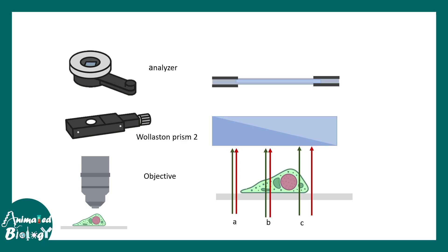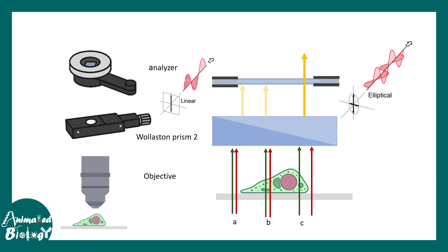Let us consider three scenarios A, B, and C. In scenario A, both ordinary and extraordinary light pass through the slide and reach the second Wollaston prism after the objective. In scenario B, both beams pass through regions of the same refractive index, so there is no optical path difference. In scenario C, there is an optical path difference because the ordinary and extraordinary light pass through regions where refractive index and thickness are very different, so beam C is retarded. This optical path difference creates elliptically polarized light, which can cross the analyzer, while the linearly polarized light from scenarios A and B is blocked. This is how the DIC microscope works overall.